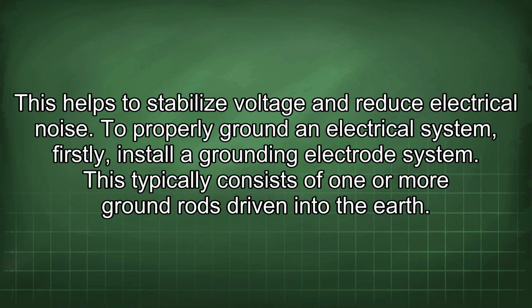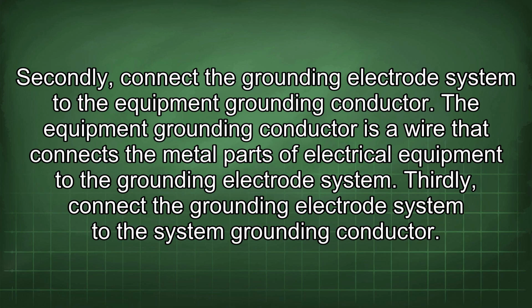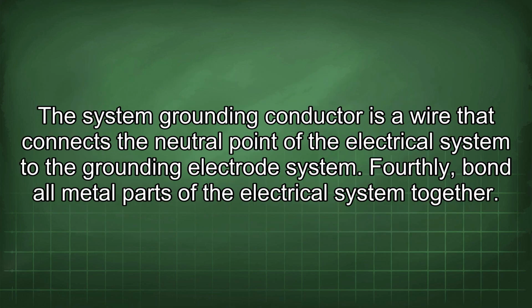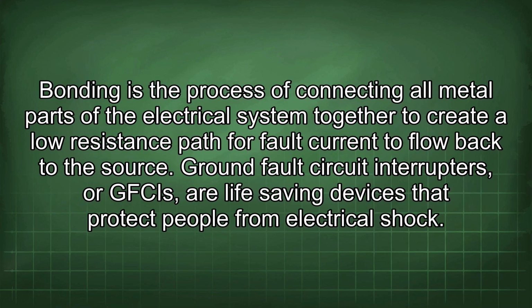To properly ground an electrical system, firstly, install a grounding electrode system. This typically consists of one or more ground rods driven into the earth. Secondly, connect the grounding electrode system to the equipment grounding conductor. The equipment grounding conductor is a wire that connects the metal parts of electrical equipment to the grounding electrode system. Thirdly, connect the grounding electrode system to the system grounding conductor. The system grounding conductor is a wire that connects the neutral point of the electrical system to the grounding electrode system. Fourthly, bond all metal parts of the electrical system together. Bonding is the process of connecting all metal parts of the electrical system together to create a low resistance path for fault current to flow back to the source.